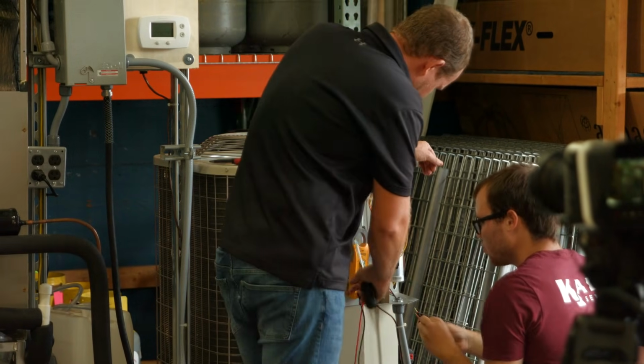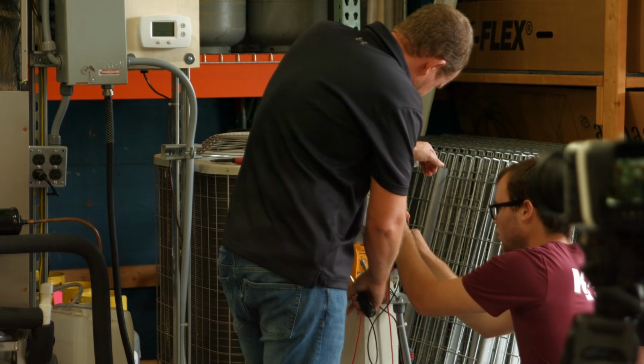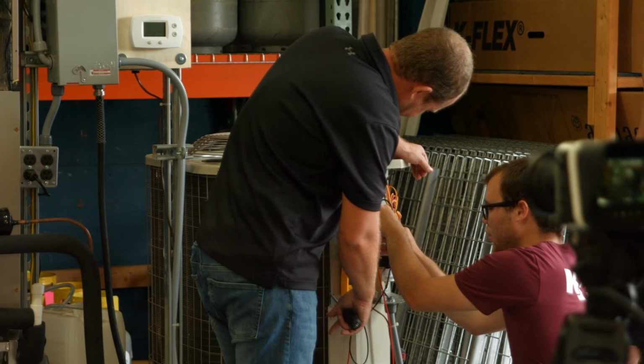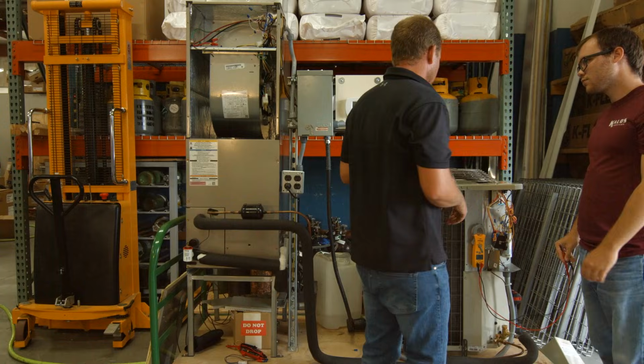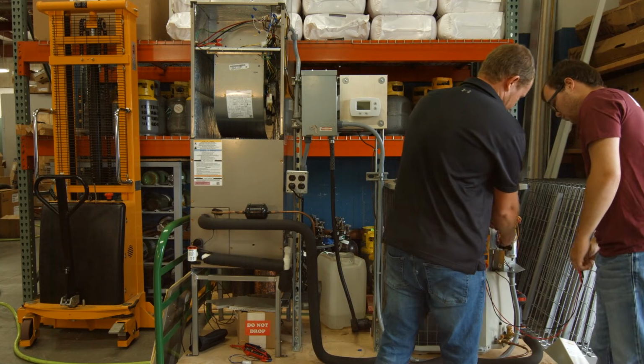So in this case, what were you just measuring between? Orange and yellow. So there's a wire not together in there. So the problem, you see we have 29 ohms, so we are getting a backfeed. You would want to go ahead and actually disconnect them. And that's the problem.